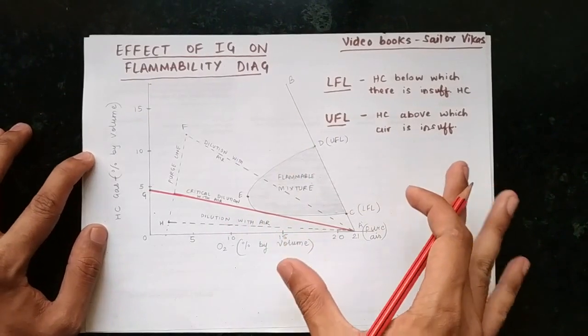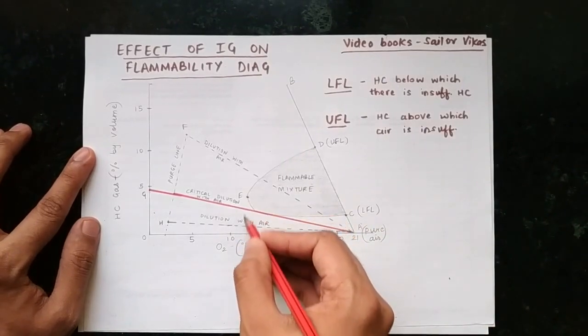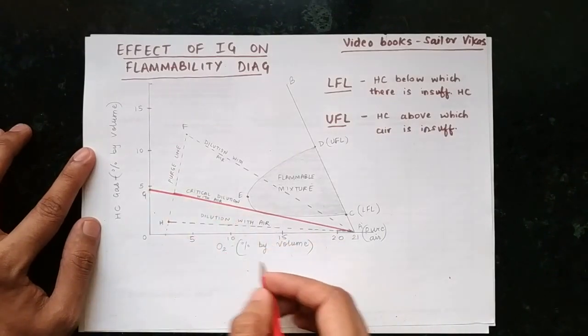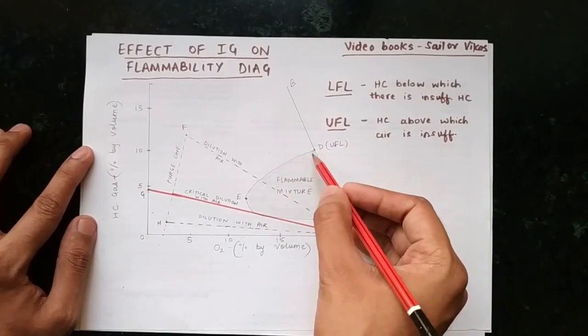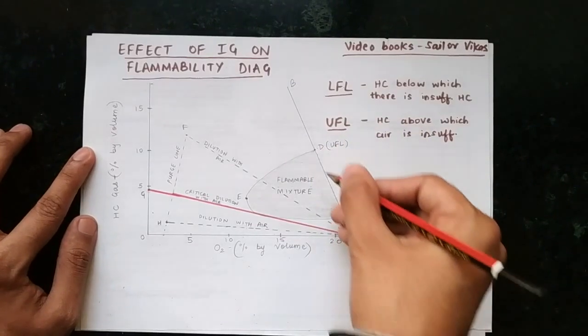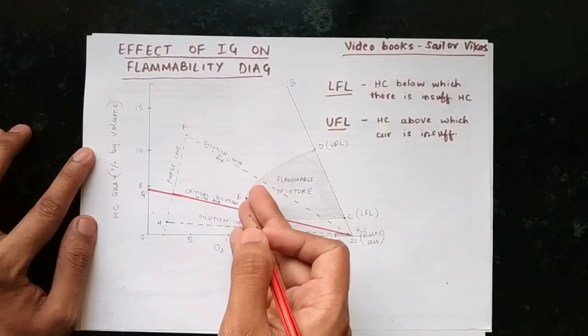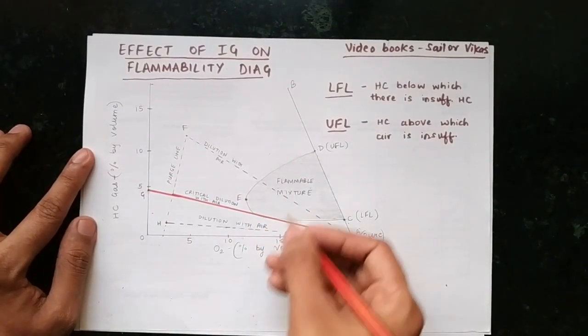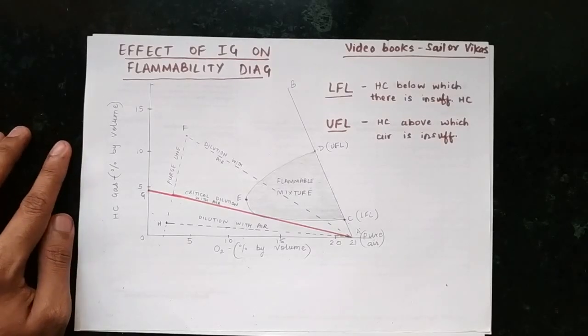Whenever you draw this diagram, always keep in mind that point E has to be approximately near 11%, and the critical dilution with air has to be approximately 4%. Also remember that lines DE and CE — if you take point D and point C and start inerting the atmosphere — they reach a common point E at approximately 11%. Further, there will be no combustion because the oxygen becomes less than 11%, and that is why we draw approximately 11% on the diagram. Thank you guys.